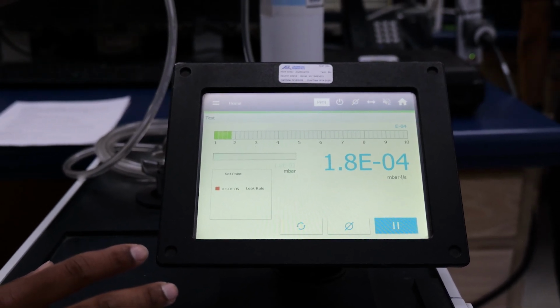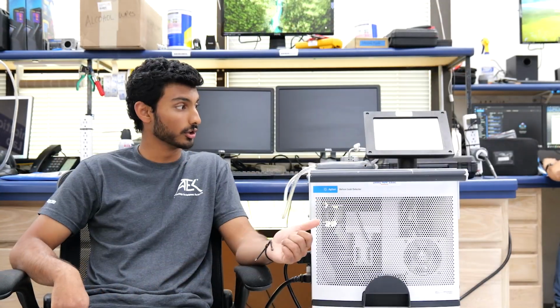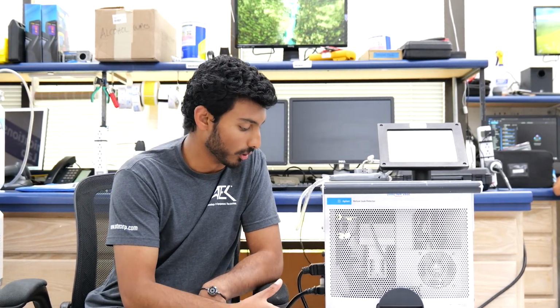per liter second leak. If you ever experience any issues with our helium leak detectors, some simple checks to do are make sure to wait at least 30 minutes before trying to do any readings. 30 minutes is usually the leeway time that I would say to get the most stable readings. Another good check is the pump condition. Make sure that all the pumps are operating up to spec. If you hear any weird sounds, that could be an indication. And as well, check the oil level.